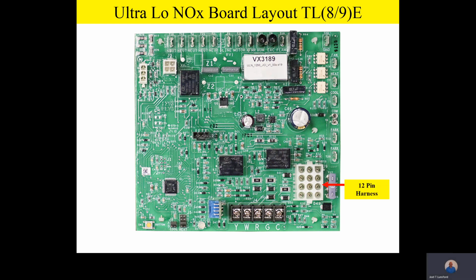Here we have our 12-pin harness. Now remember, team, the 12-pin harness is where you're going to harness in from the factory those critical components like rollout switches, pressure switches, high temperature limits, the gas valve. Those are all components that are going to be harnessed into the 12-pin harness. So these are 24-volt inputs and outputs for safety circuits, pressure switches, gas valves, etc.